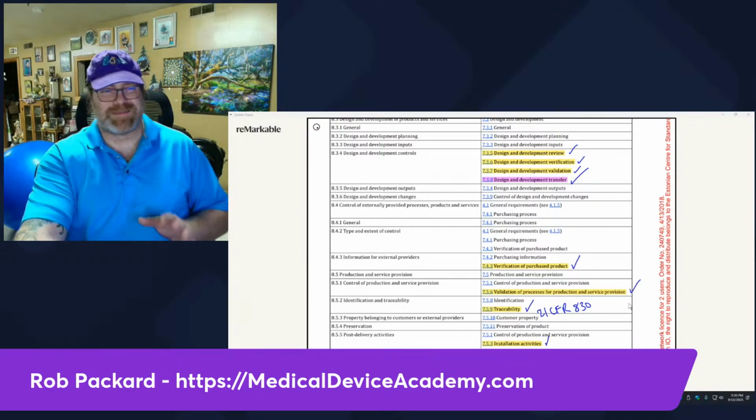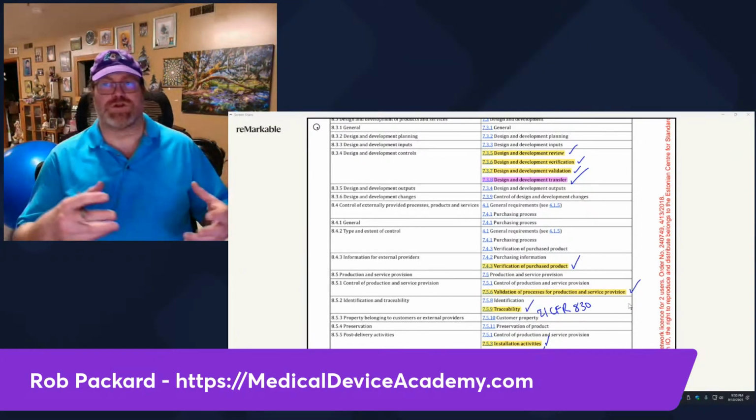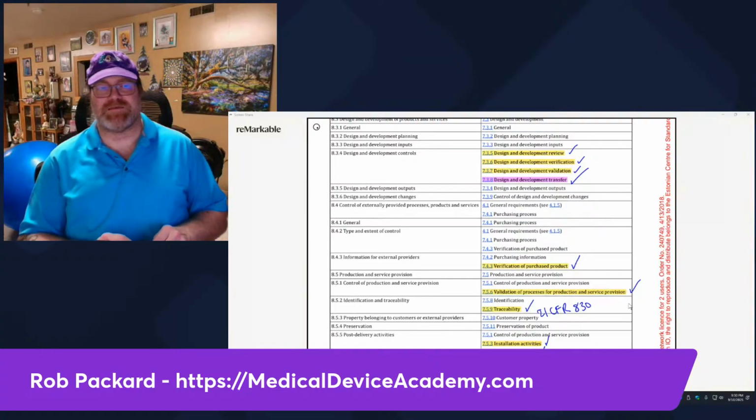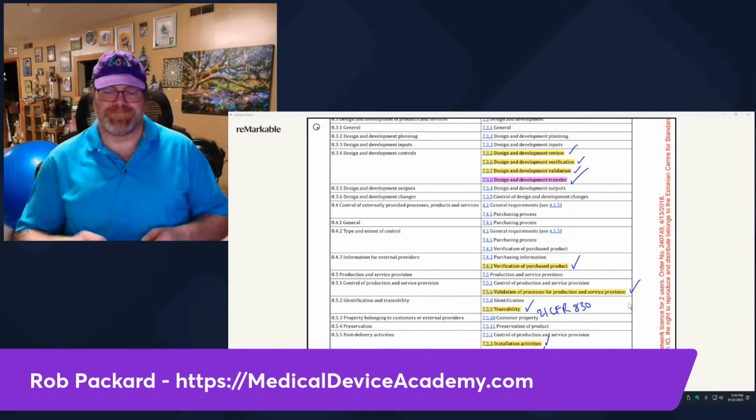Service is mentioned, but the prescriptive requirements about doing an analysis of service and determining if corrective actions are required, and doing a statistical analysis of that service data, and having records and procedures, are not all spelled out as required by the FDA or other regulators.